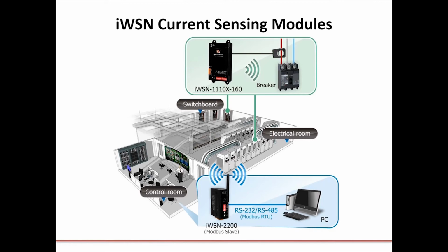Along with the IWSN sensor modules, we have the IWSN 2200 series data concentrator. This is a data logger designed to work with the IWSN sensor modules and can capture data from up to 31 of those modules. It also acts as a communication gateway between an RS-485 network and the 433 megahertz wireless network.